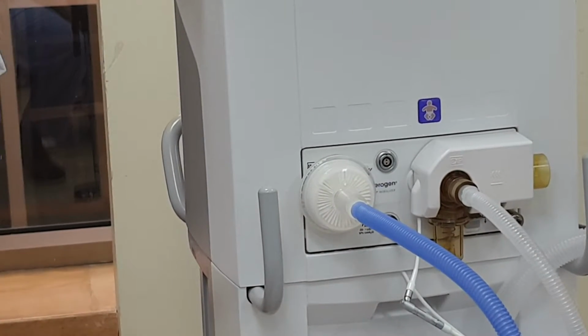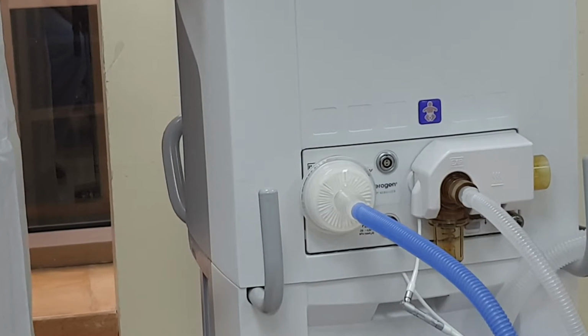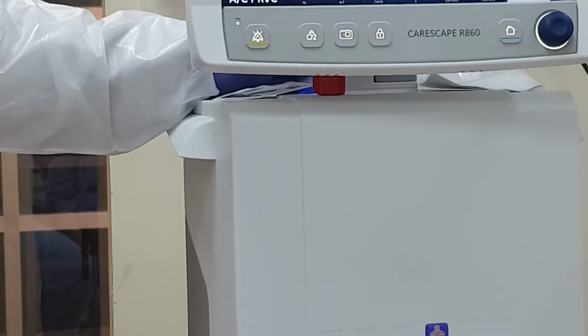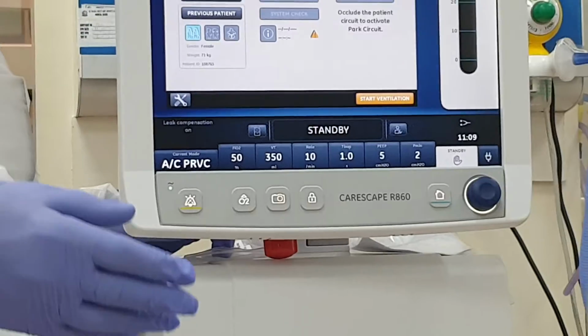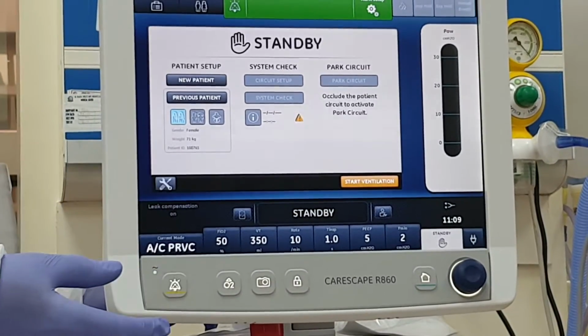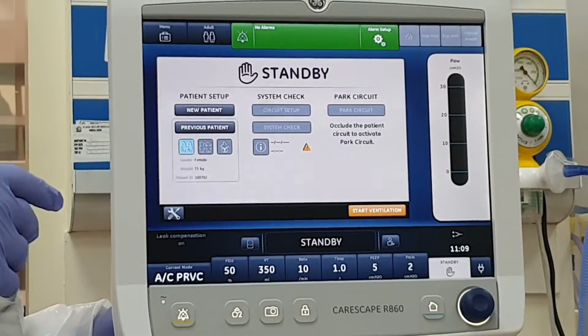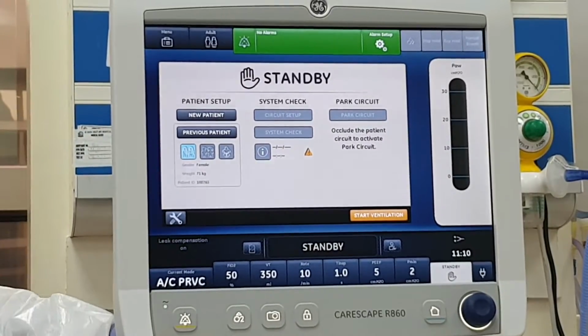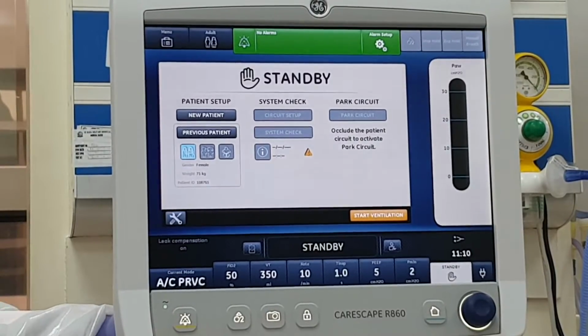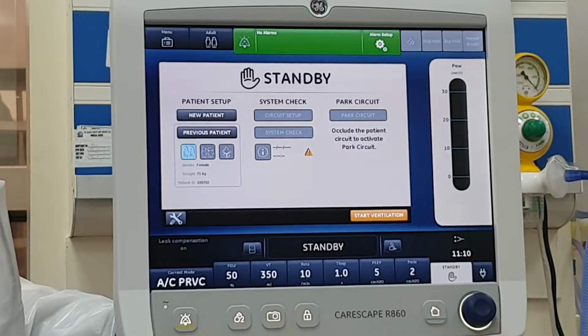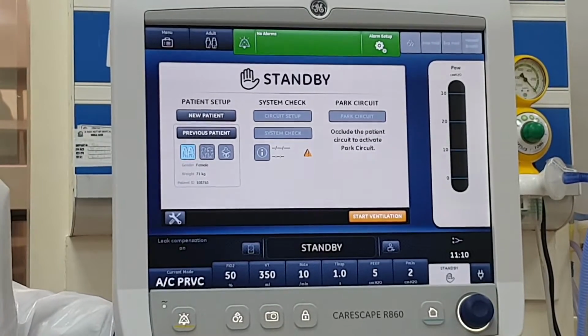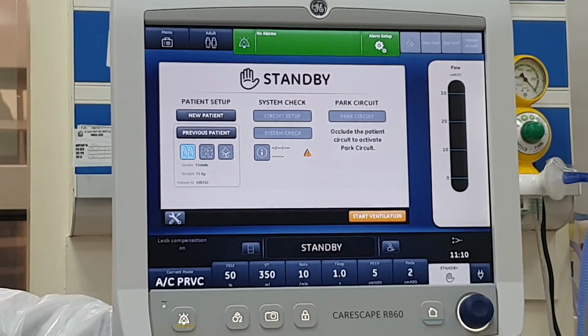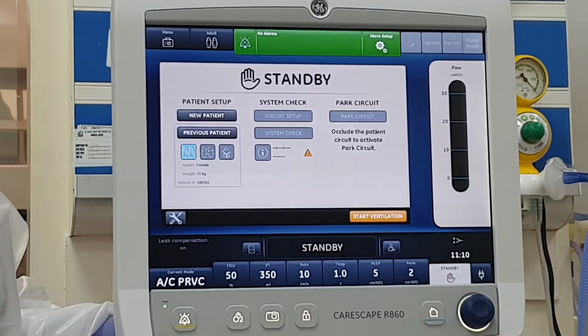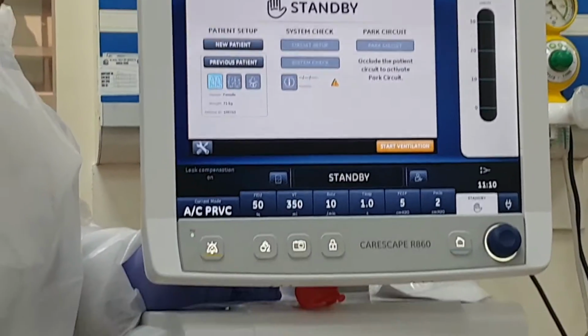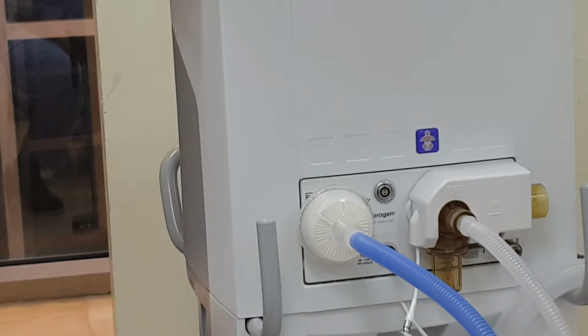Most of the ventilators, sometimes they do have this filter inside the machine. So when there is an internal failure or issue, basically the machine or the ventilator will go to the biomed, then they will open it, take the filter away, put another one, and bring it back to the ICU, which takes time and effort. But what GE did, they made it very simple and easy. Anytime there is an internal failure, you could replace it. It can be used between patients. There are valid studies that show it to be a protective part for the internal part of the ventilator.